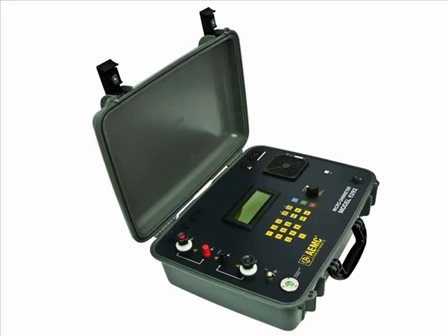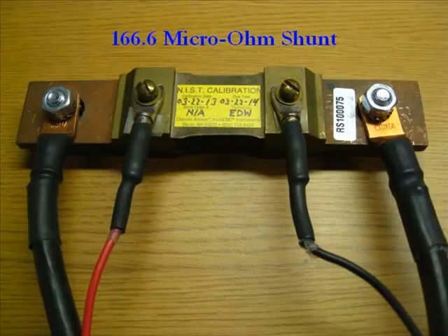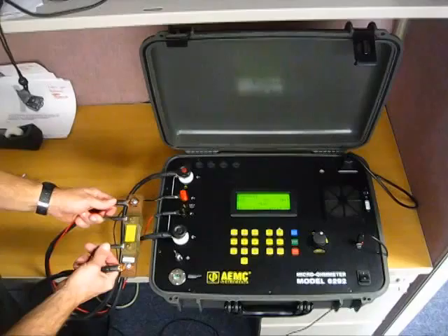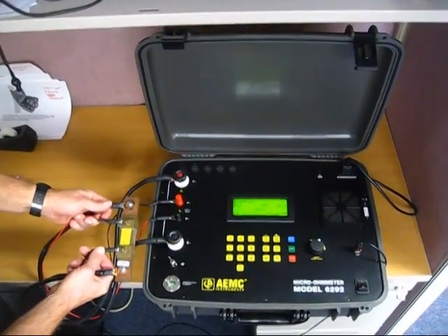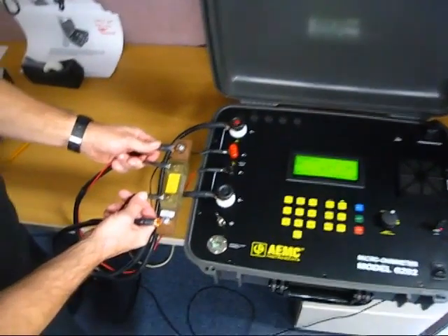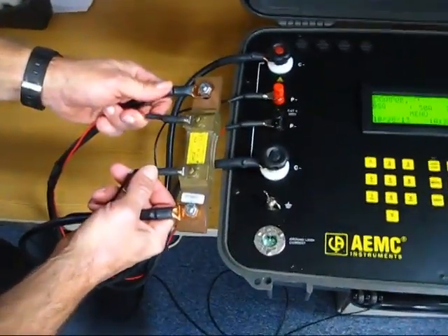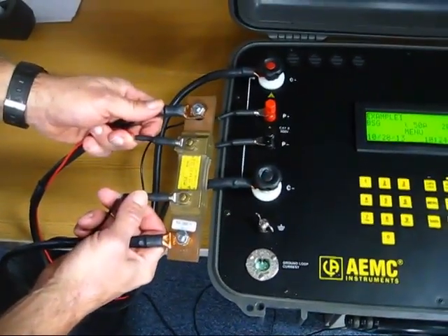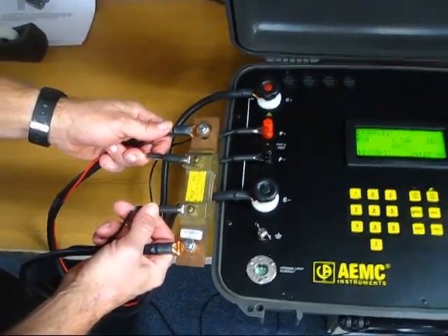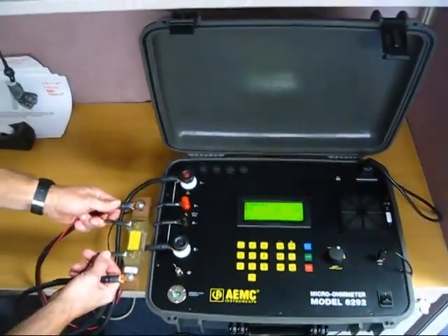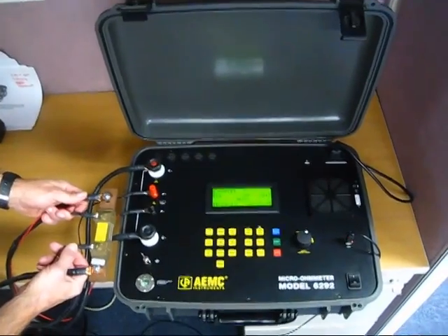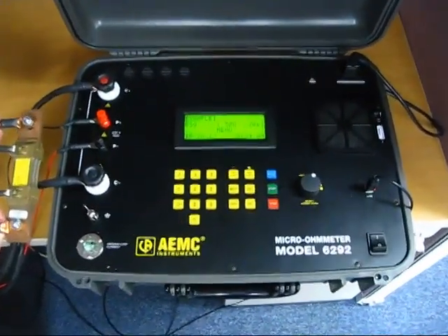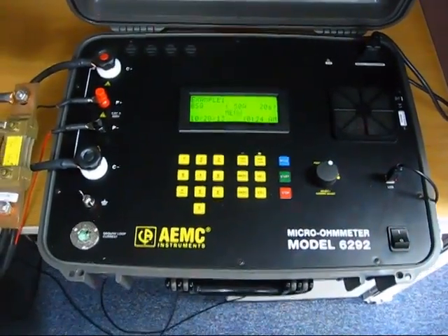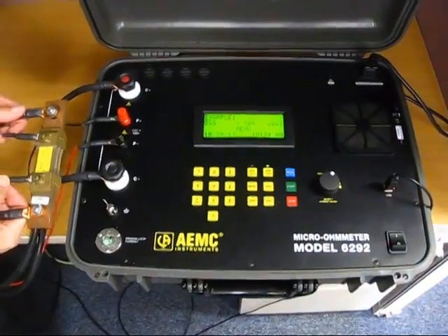Here's the 6292, and we will be using a 166 microohm shunt for the test, shown here. For our demonstration, we have connected a 166 microohm shunt to the instrument. For this test, we will run a 20-second test in normal mode with a current of 50 amps. During this test, we will take partial measurements at 5-second intervals and store the results in the instrument's internal memory.